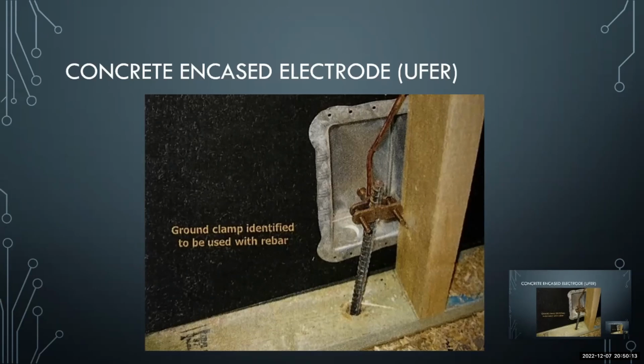So a follow-up to that. A grounding rod encased in concrete, such as a walkway, is not a UFER. Is that right? That's right. A UFER has to be a minimum of 20 feet encased in the concrete. It doesn't have to be one continuous piece. It can be tied together with steel ties to make 20 feet, but it has to have a minimum of 20 feet in the concrete.